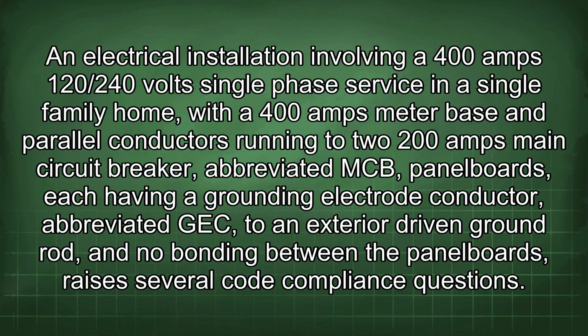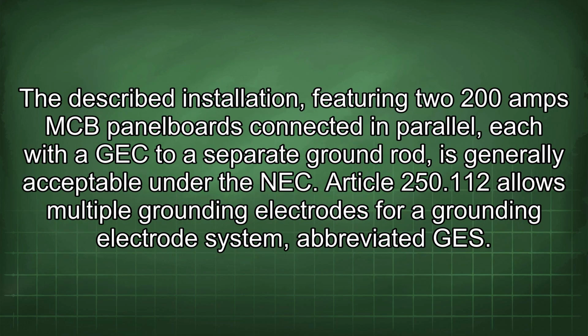120/240 volt single-phase service in a single-family home with a 400 amps meter base and parallel conductors running to two 200 amps main circuit breaker, abbreviated MCB, panel boards, each have a grounding electrode conductor, abbreviated GEC, to an exterior-driven ground rod, and no bonding between the panel boards, raises several code compliance questions. The described installation, featuring two 200 amps MCB panel boards connected in parallel, each with a GEC to a separate ground rod, is generally acceptable under the NEC.